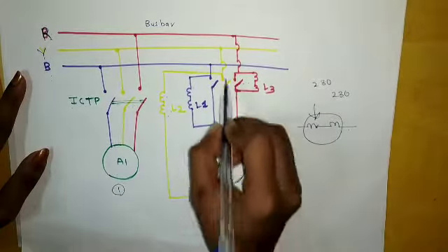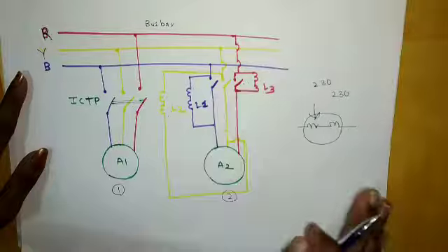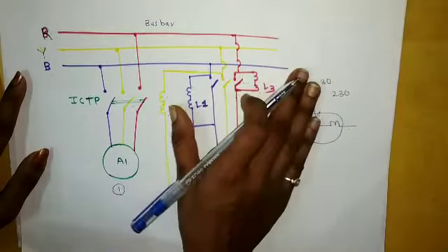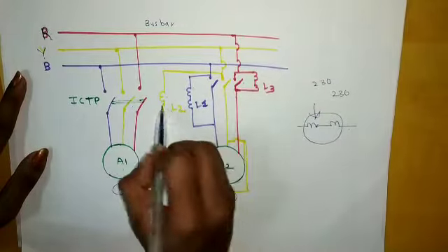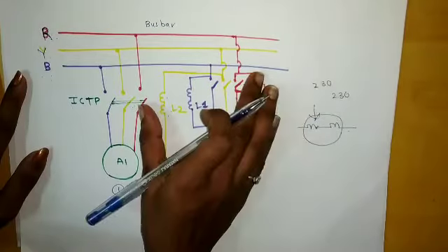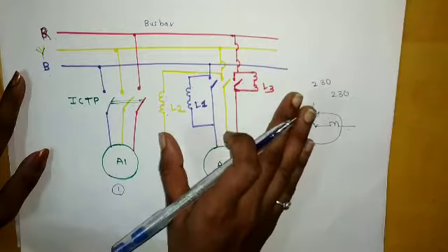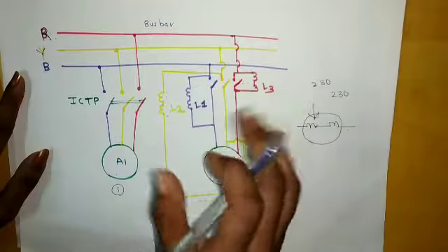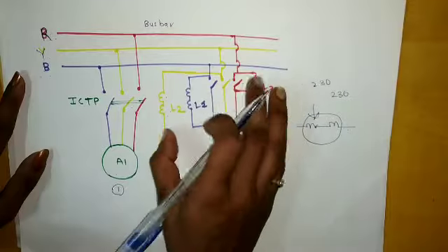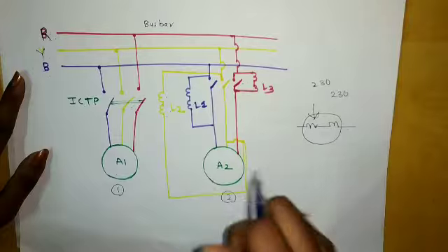Now I have connected lamps as per the given phases. What will happen? The lamps will glow. If the lamps glow in this sequence, that this will glow bright, this will be dark, this will be dark, then there is something wrong with our phase sequence. If all three lamps glow bright at the same time, then our phase sequence is okay.